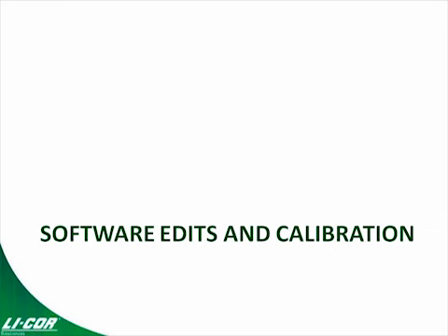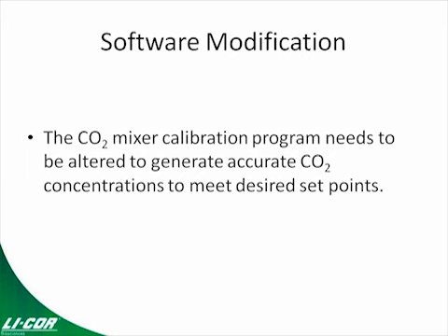Any software that you have on your 6400, the files are all going to be in the same location, and there's going to be slight differences in some of the menus, but the software modification is identical as far as the things that need to be done. The software edit is necessary for any systems operating 6.1.3 or older. Newer systems, as shown here, have slightly different menus than older systems do, but all the steps are the same.